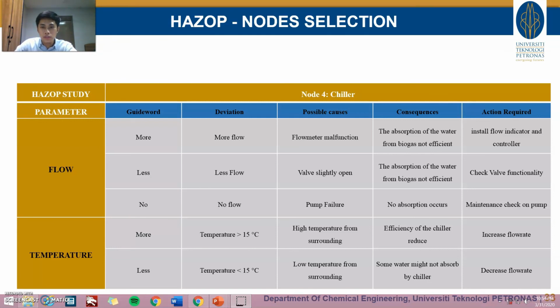Less flow, possible cause, valve slightly open. Consequence, the absorption of the water from biogas is not efficient. Action required is to check valve functionality. No flow, the cause is pump failure. Consequence, no absorption occurs inside the chiller. Action required is to do a maintenance check on the pump.